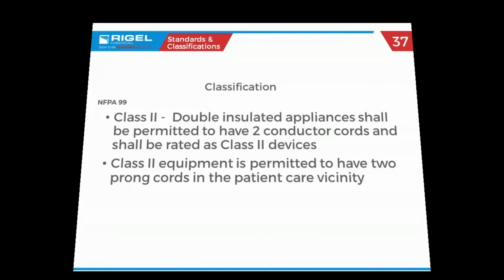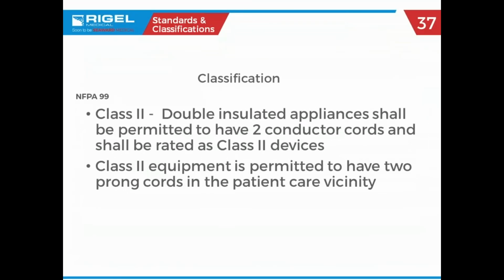Category 4. So classifications, just like we talked before, Class 1, Class 2. Class 2, double insulated, the box within the box, got the chassis and the plastic housing around it, shall be permitted to have 2 conductor cords, so you don't need ground. We're not counting on a ground wire to provide that path to shunt off any leakage or touch current. So only 2 prongs, and also within the patient care facility. And there's something coming up here again that will be maybe surprising to some of you.